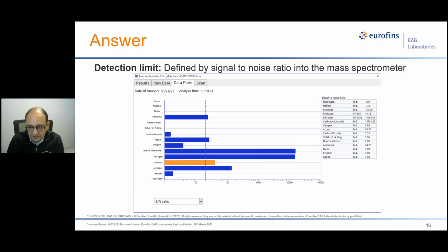So this is a little bit of information on how the detection limit can be determined. On top of that, I would like to add that this detection limit can be optimized for individual gases. For example, for fluorocarbon, our detection limit is 50 ppmv, so we can measure anything above 50 ppm. But if we have a specific calibration for that gas, we can also go into the 10 to 30 ppm level of measurement.